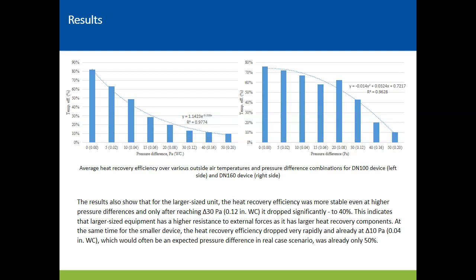But in general, the results state that if we look at this measured heat recovery efficiency, the datasheets only represent the first couple of seconds when this device works. Then actually this efficiency is the stated 85, 90%. But already at the middle of this cycle, something like 30 seconds, the actual efficiency is already dropping down to 70, 60%.